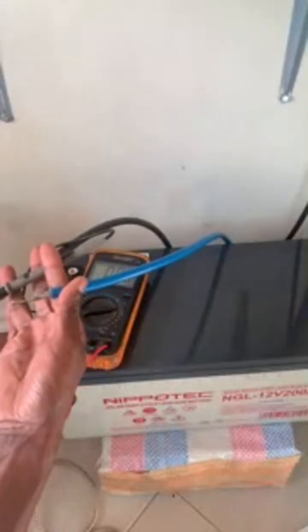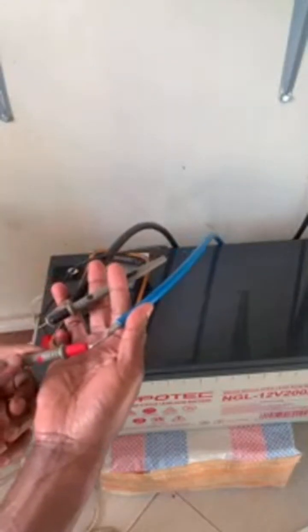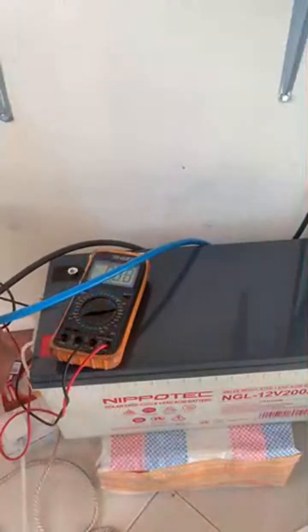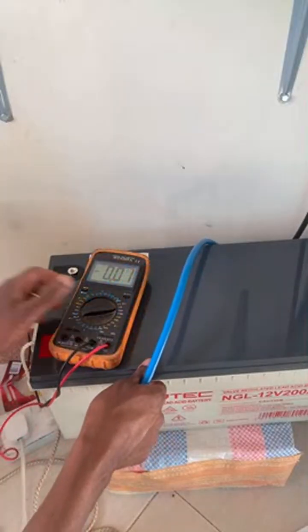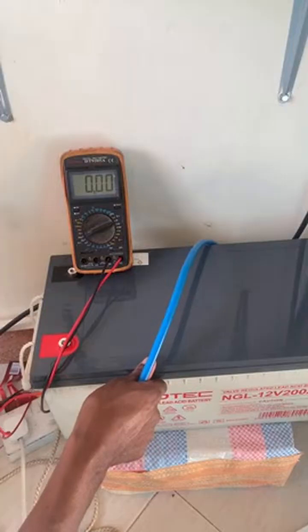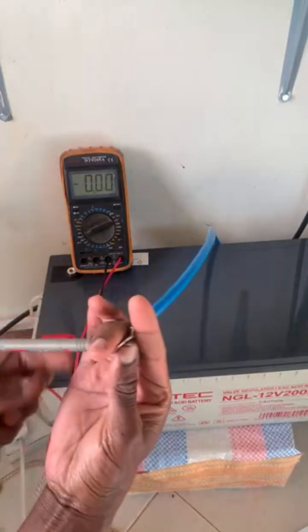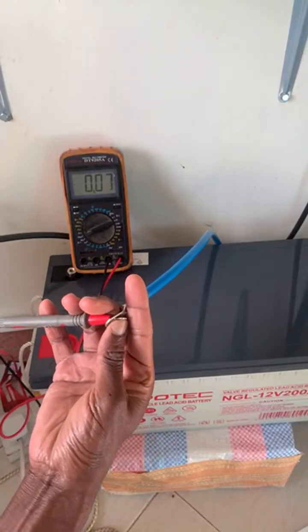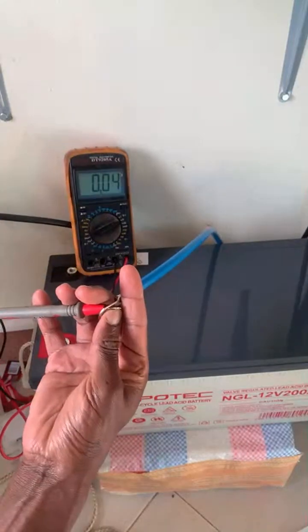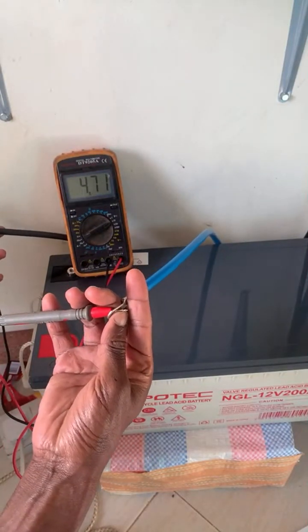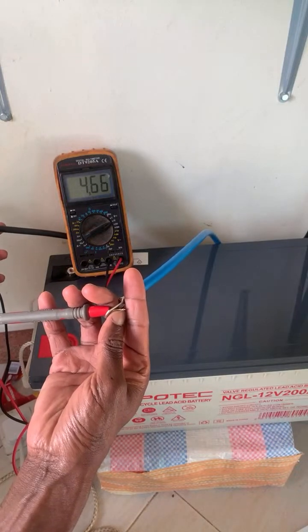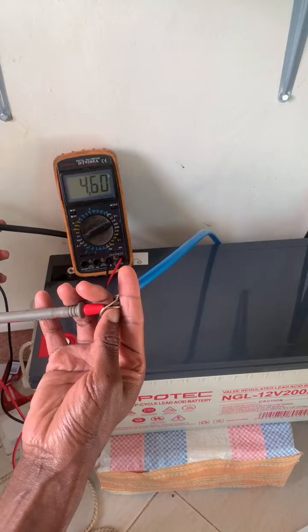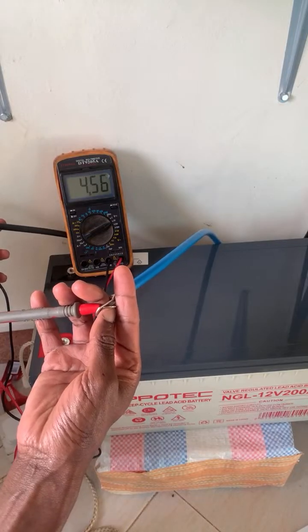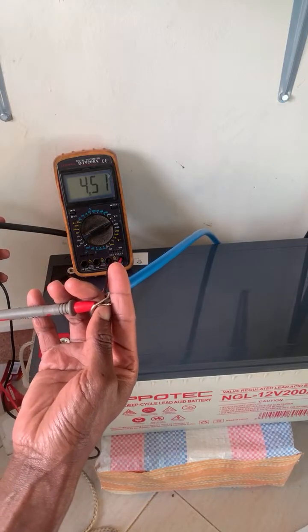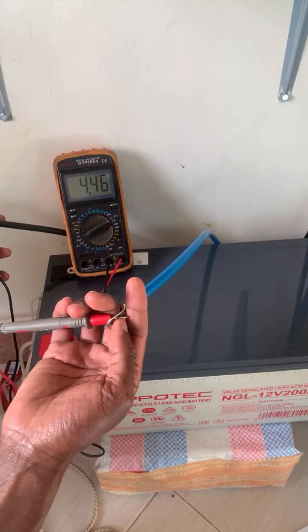Why? Because we don't have AC coming in, we also don't have DC coming in from solar, and therefore we do not have any power that is generated. Now if I take this digital multimeter and place the red probe at the positive terminal going to the inverter, and the black probe, we get a reading right there. Why do we have a reading? This is from the inverter. And remember, the inverter is not connected to PV or solar, inverter is not connected to AC, but we have some reading, and the reading is reducing slowly by slowly.